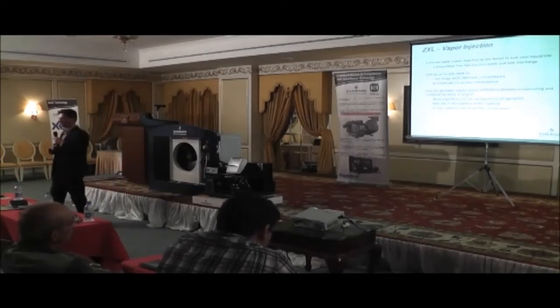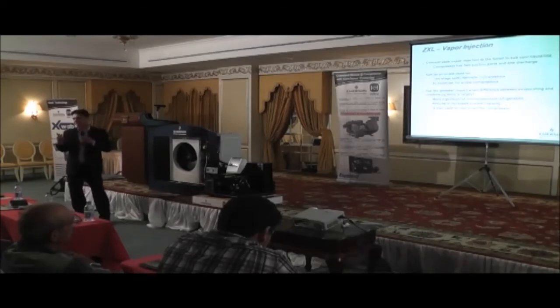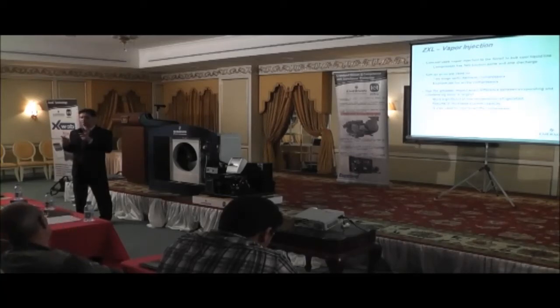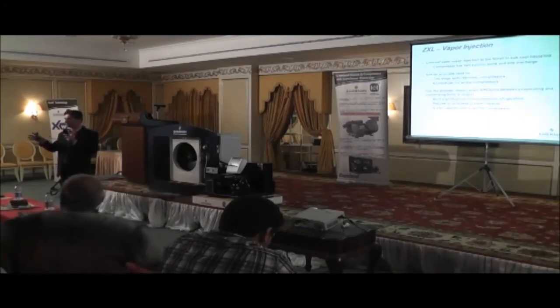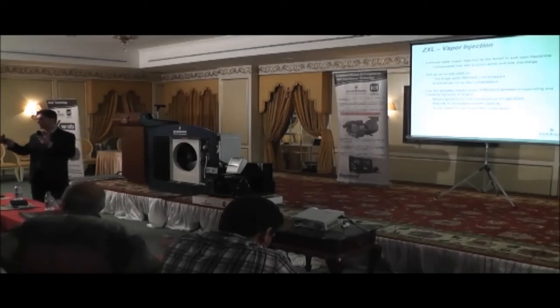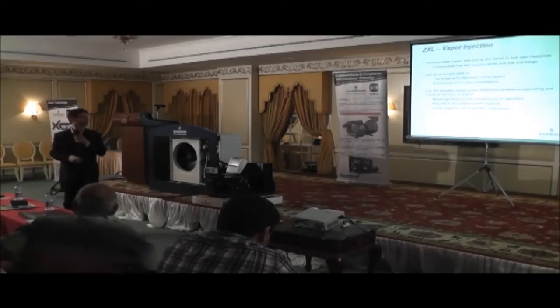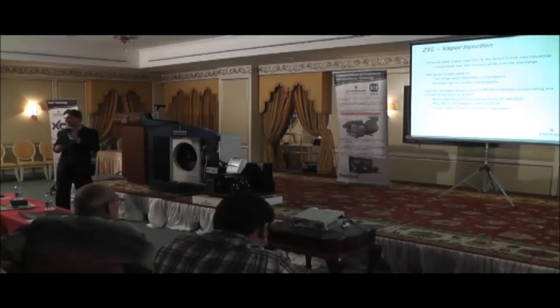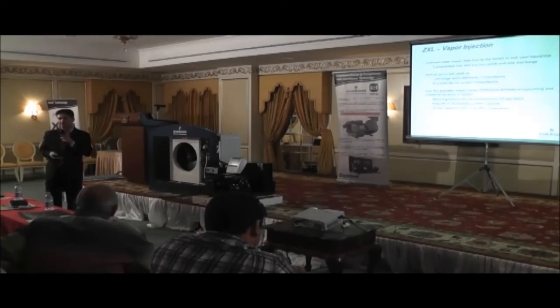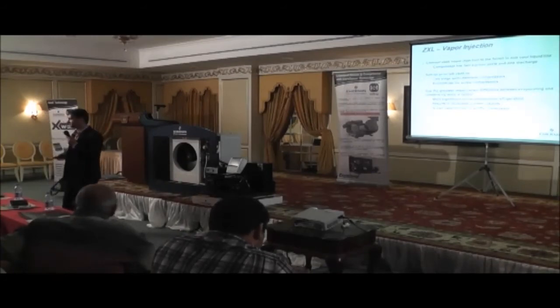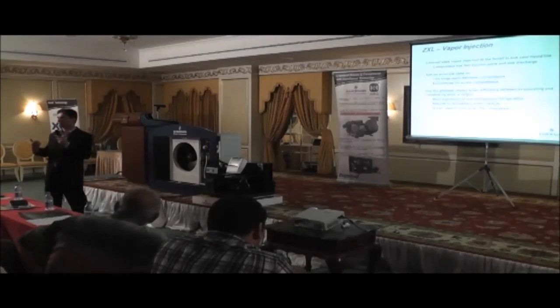Now, for the ZXL, we have what we call EVI, which is enhanced vapor injection. With this design, the compressor has 2 suction ports, 1 discharge. And the concept, I don't know if any of you have worked on 2-stage compressors that have a subcooler, is basically the same thing. We've taken the concept of a subcooler on a 2-stage compressor and we've applied it to scroll. One of the reasons we do that is by using a subcooling circuit, we increase the capacity of the unit and it gives you much better efficiency. Secondly, by using the subcooler, we keep the compressor cool so it doesn't overheat.